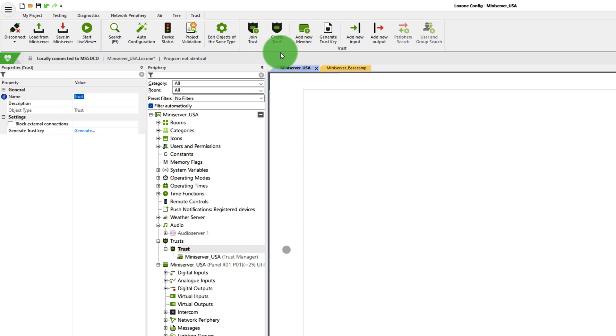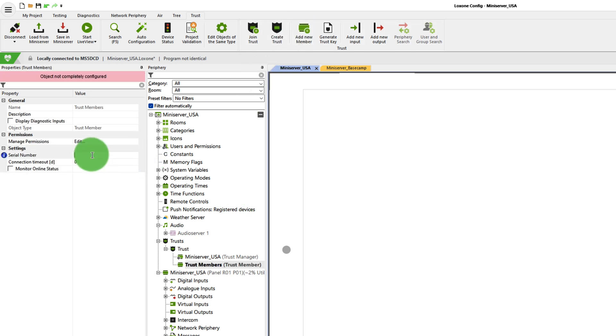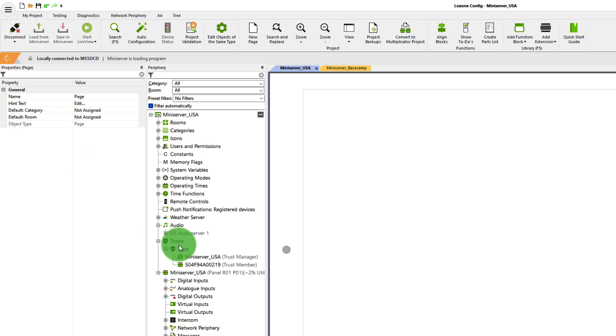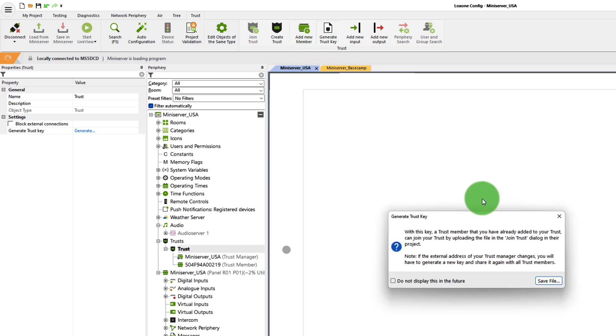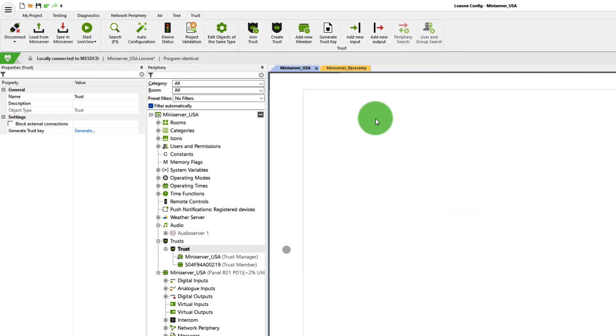Next, add a mini-server to the Trust as a participant. To do this, simply click on Add New Participant in the menu bar. In the properties of the created participant, you'll now enter its serial number. Since the participant has not yet joined the Trust, its name is also not known yet. In this way, it's very easy to add further participants to the created Trust. Next, a Trust key must be generated to allow the participants to join. Simply click on Generate Trust key in the menu bar. This will create a file which must then be saved. You can now send this file, for example by email, to the administrator of the participant mini-server so that he can join the created Trust.